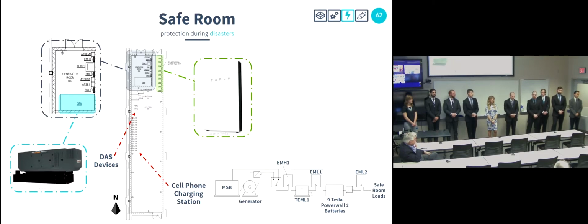The reason it's located there is due to FEMA requirements that the generator needs to be in as secured an area as the safe room in case of a natural disaster, which is why we went with the enclosed area adjacent. An enclosed area is fine, but you end up with an enclosure within the enclosure—the house itself isn't really necessary.